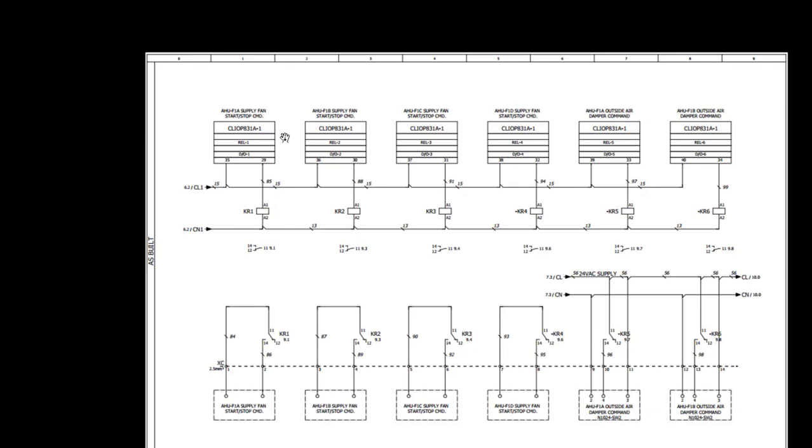Then how is the wiring done? Here we are using a relay between the module and the terminals for the command. Why are we using this relay? This is optional if your module is supporting 230 volts, but in our case this module only supports 24 volt AC to be passed through the relay contacts, while the voltage from the MCC panel was 230 volts.